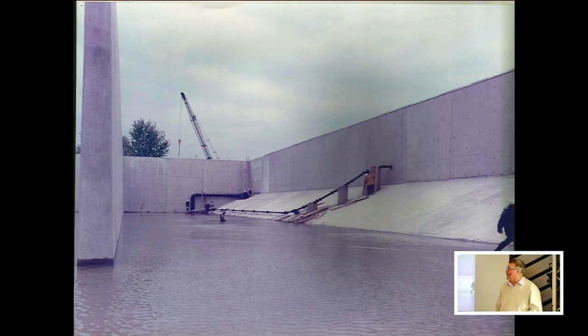And there we go. That was the new reservoir, the east reservoir, built towards Chorlton Road. So road level, part way up at the top of the slope, and that bit underground. Because ground conditions there were that bad, we had to have the reservoir designed and constructed like the hull of a boat, because there's a lot of running sand underneath. There's a complex system of drains to make sure the water pressure doesn't build up and pop the reservoir out of the ground. But just in case, it sits there and can float on a certain amount of water as well. So a lot of design goes into these huge structures that appear next to residential areas.